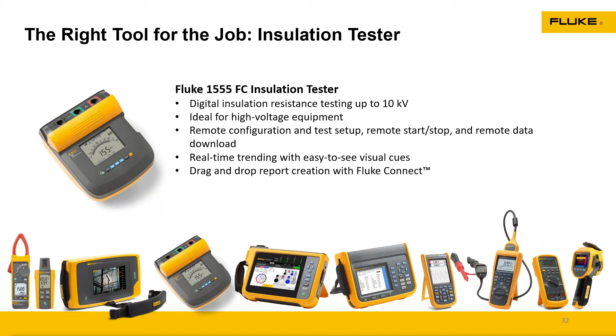Insulation testing is also critical. There's a known practice that we want to double the value of our insulation test based on the voltage. What I mean by that is Romex wire for our houses. It's basically 14 gauge, 2 wire with a ground on it. Even though we put that in our house at 120 volts, that wire is actually rated for 600 volts. We would want to double that value. So in a sense, we would do a 1200 volt insulation test against that type of wiring. The larger the conductors, the larger the output voltage would need to be during these types of insulation tests. Good practice, just wanted to throw that out there as well.